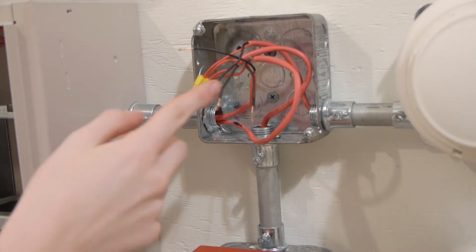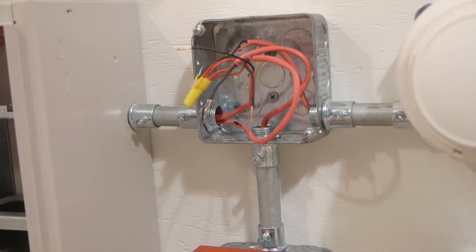Now we want to find the one coming from the panel, which is this one right here, and separate it. These remaining three right here are three legs of the SLC coming off of this junction. If your ground fault has not gone away, that means your ground fault is between your very first junction and the panel, which probably means a chafed wire, water damage, or an internal ground fault on the panel.